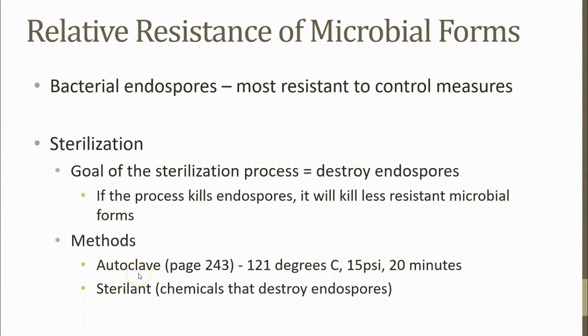Using an autoclave uses steam and high heat. The goal is to reach 121 degrees Celsius and hold the pressure at 15 pounds per square inch, maintained for 15 to 20 minutes. If we hold it at that temperature and pressure for 20 minutes, we can guarantee those endospores will not be viable. Ethylene oxide is one of those gas sterilants that can be used to destroy all matter of life.